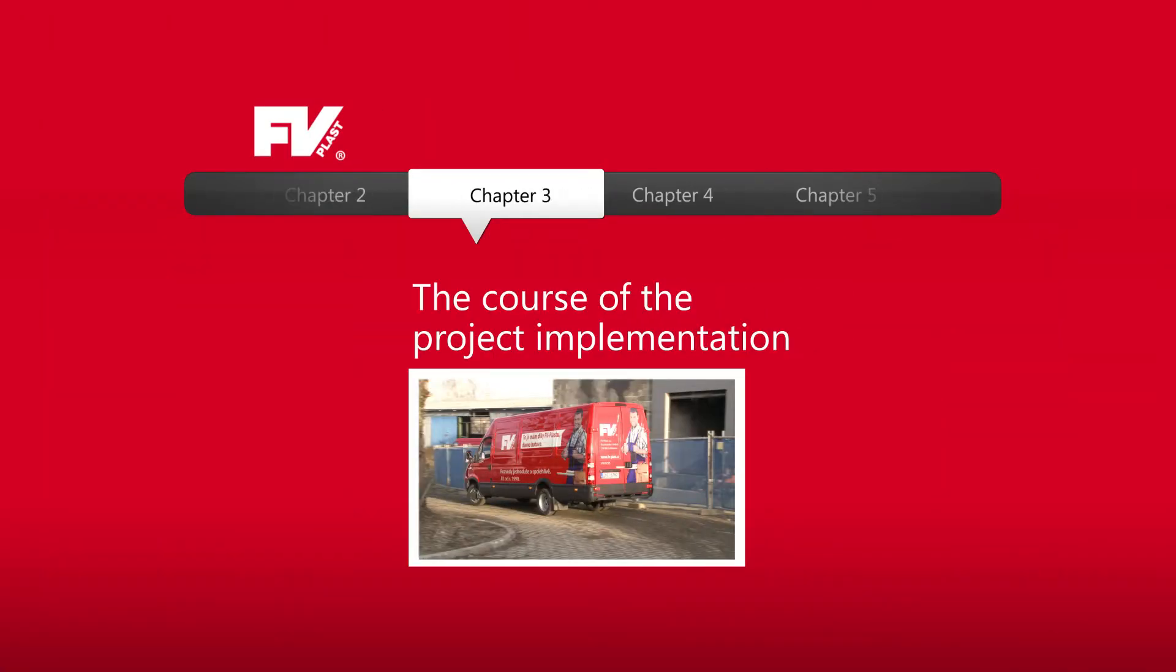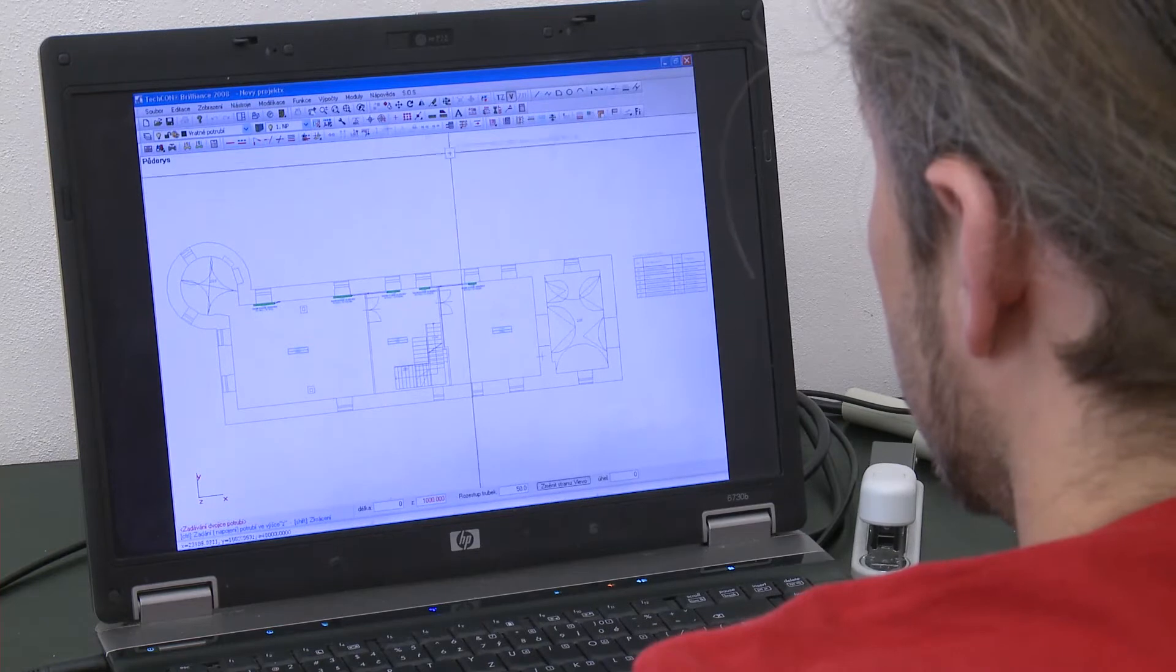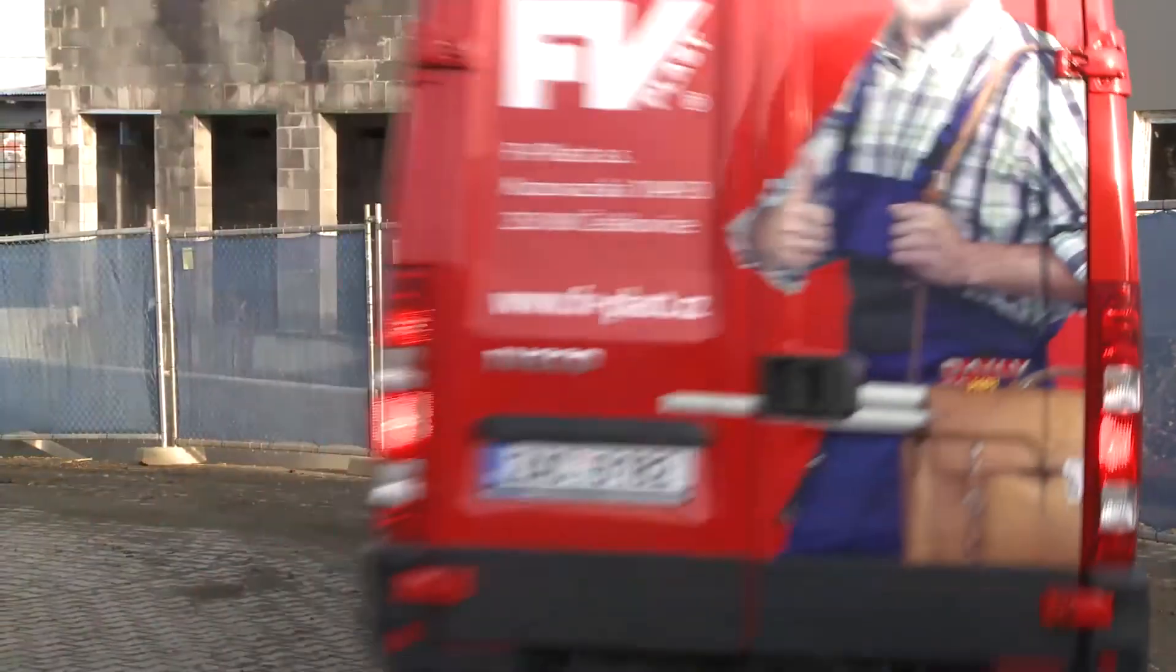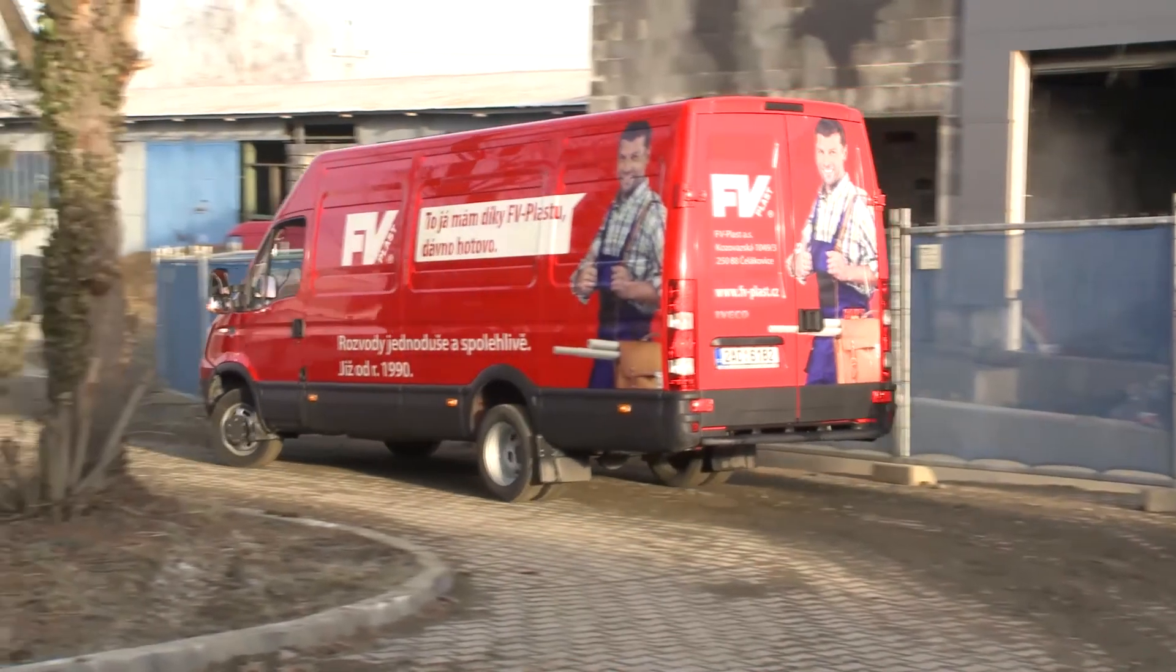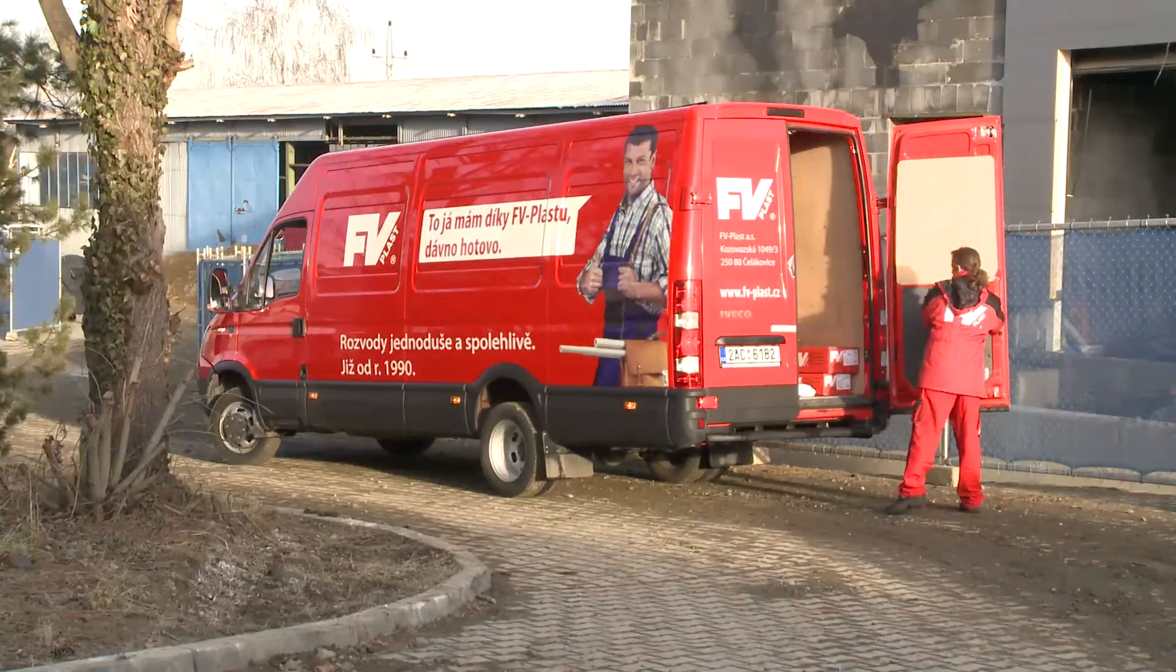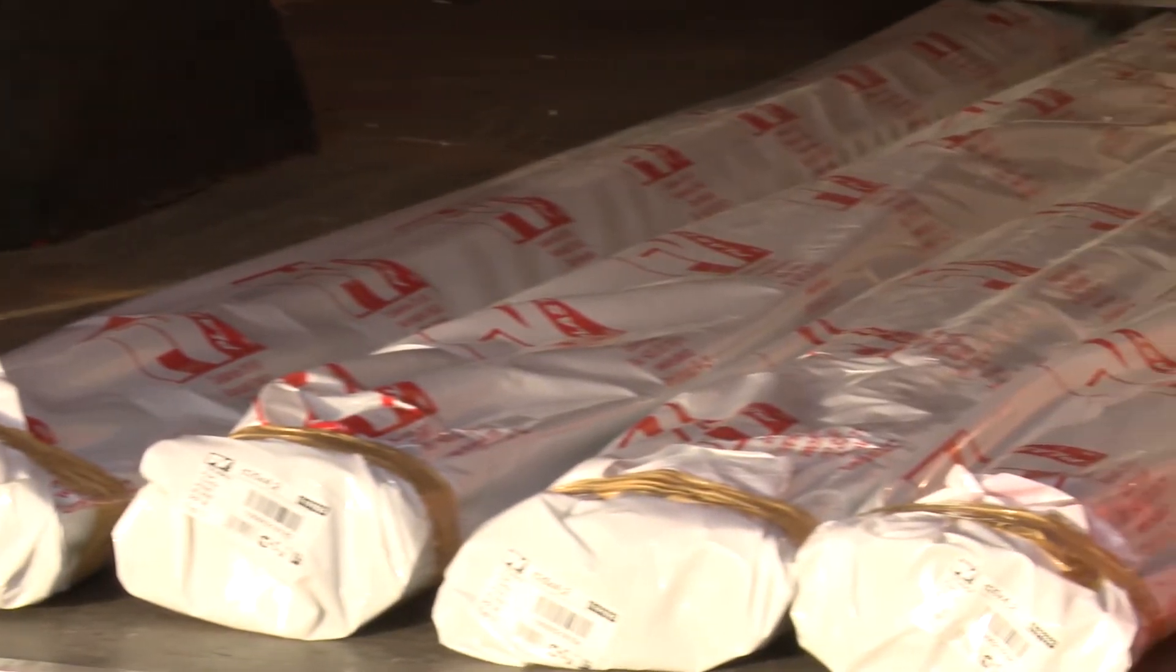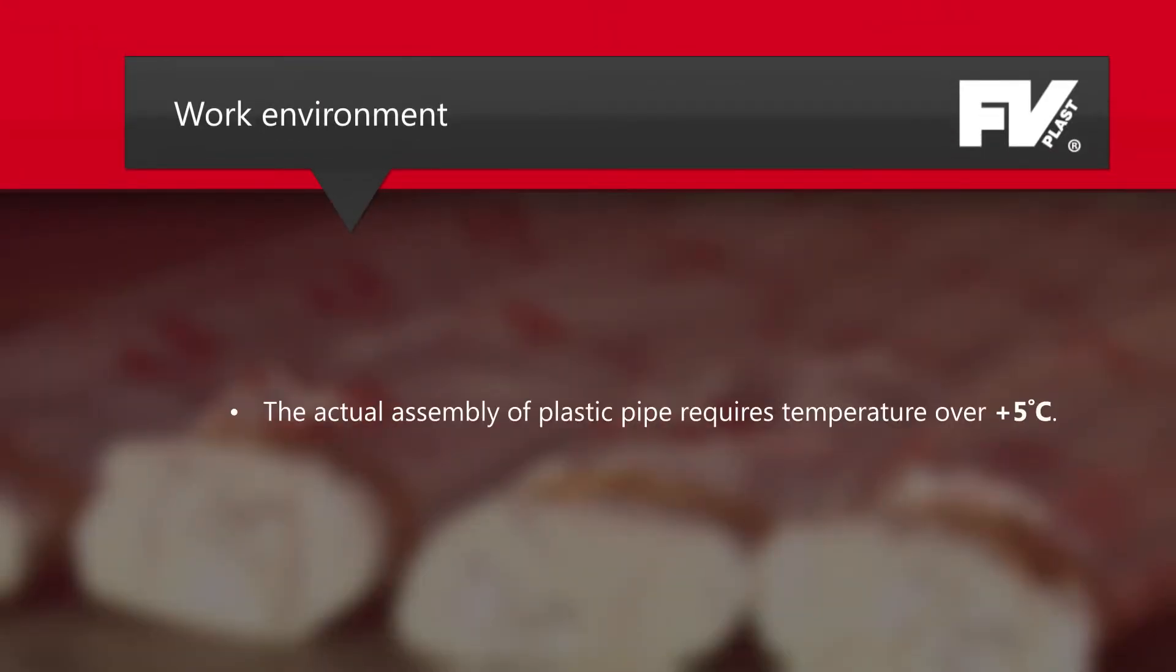Before start of implementation it is very important to develop a project. We provide designers with our own calculation program for designing, FV CAD. The actual implementation begins with the transport of elements to the site and their storage. The products of FV Plast are packed in high quality protective packaging which we leave packed until assembly. The actual installation of plastic pipes requires temperatures over plus 5 degrees centigrade with respect to material and ensuring of optimum welding conditions. For these reasons the work environment on site must be warm.